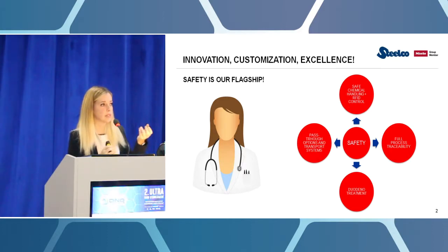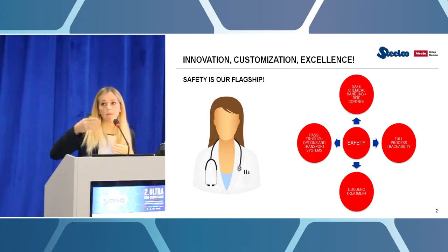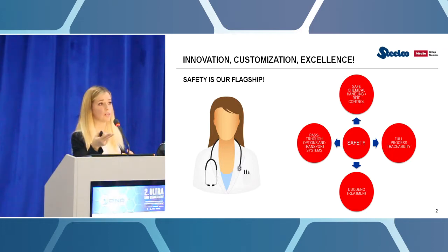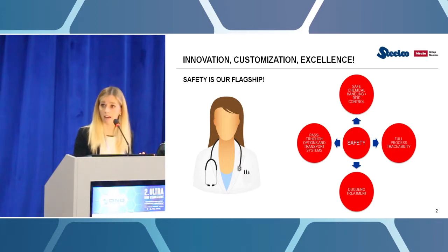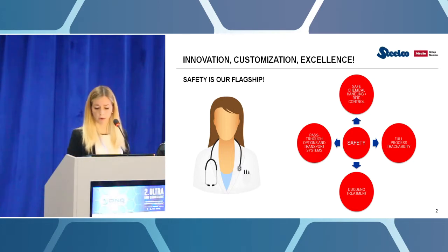It's a system that reads the label of the chemical and communicates directly with the machine, so that if, for example, by mistake you put the wrong tank inside the machine, or you invert the detergent tank with the disinfectant one, the machine will recognize that automatically, stop the cycle, and won't let you go ahead. So this is also a safety feature present in our washers.